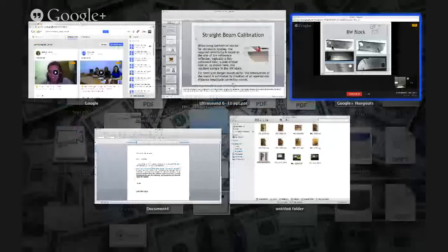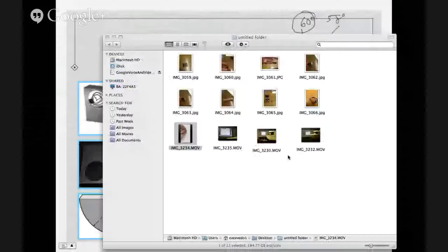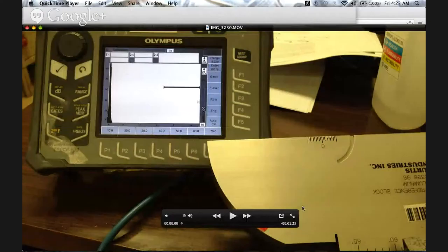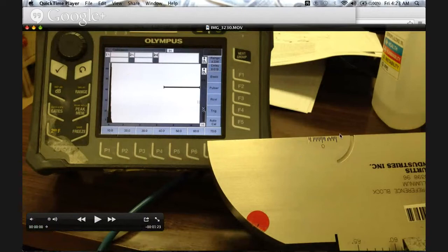So, for example, you see the numbers here, 60, 65. If I line up my zero here, if I put a standard 45-degree transducer and align my index line to zero, I should get the maximum signal. If I don't get my maximum signal, but my index line is maybe in front or behind it, then maybe I'm not exactly at 45. You understand?